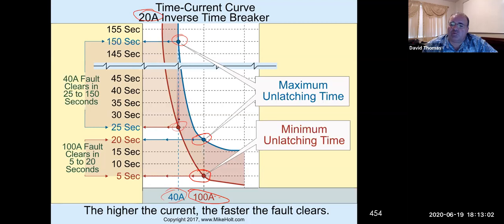The wires possibly will get hot, but not enough that it will burn down the building during that time period. It's just something to think about. The higher the current, the quicker this thing will trip. The lower the current, the longer it's going to take to trip, between 25 and 150 seconds, right? Versus 5 to 20 seconds for this 100 amp scenario, okay?